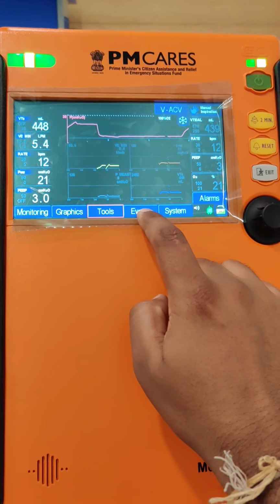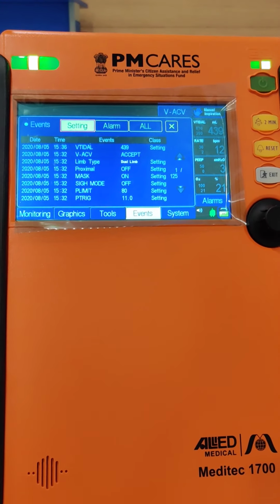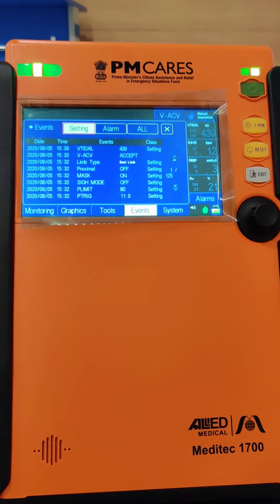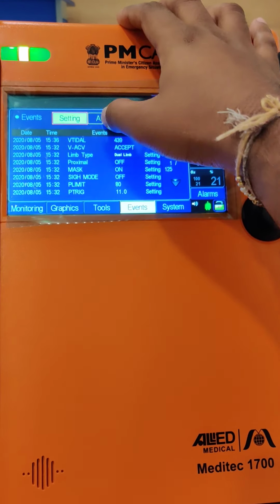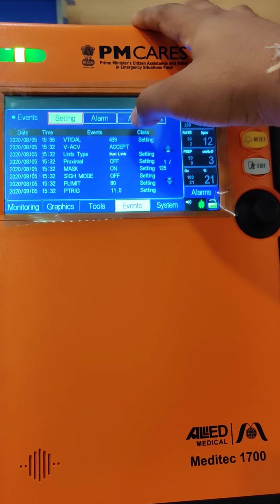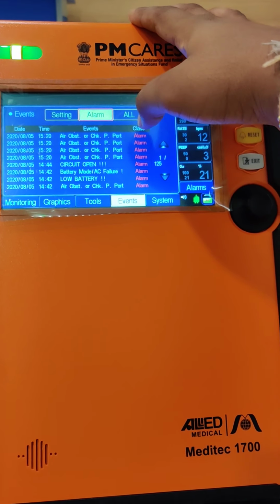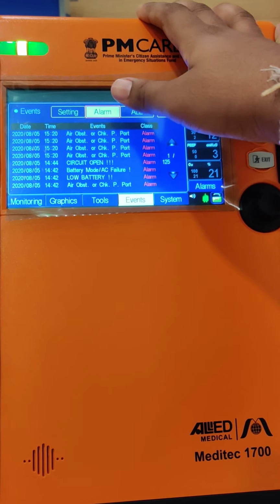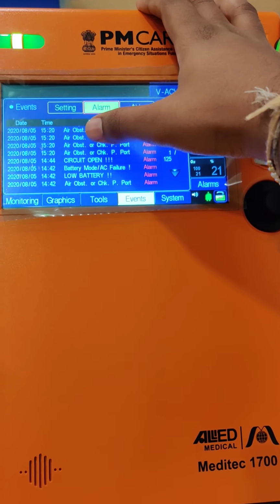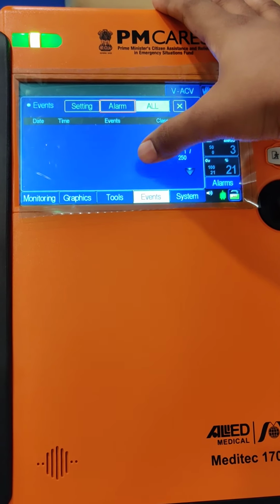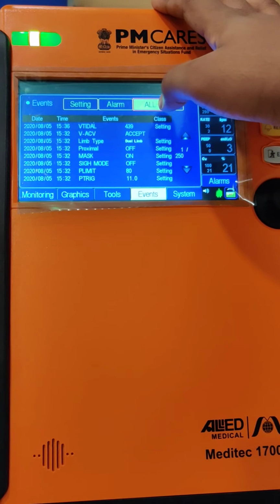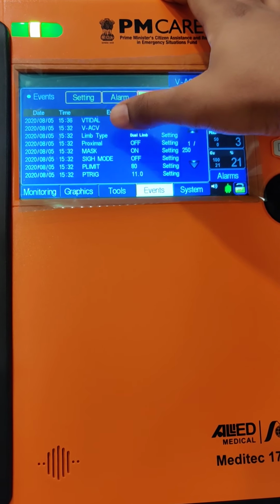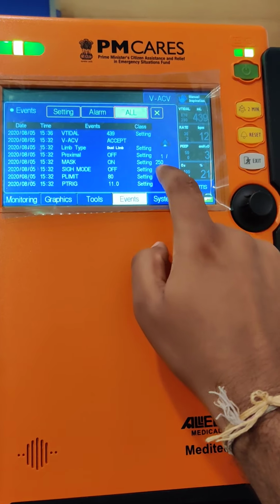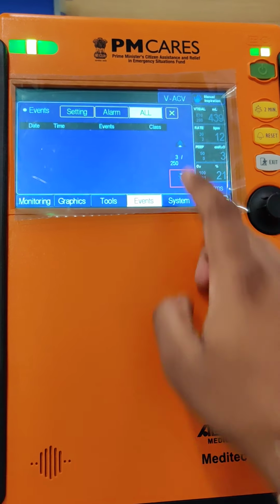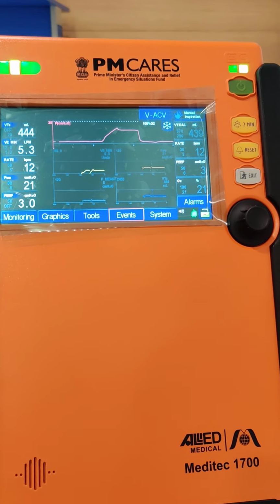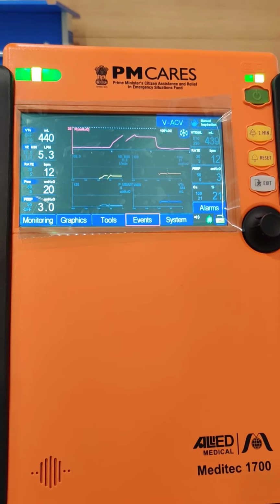Now coming on to the next shortcut key, this is the events. You can see the history logs, both for settings and alarms, whatever settings you have made in the past or whatever alarms have come up. You can see these alarms with the time and the date. If you select the all button over here, you will get the display of both the alarms as well as the settings. It has a 2000 alarm history, so you can see the past history and the alarms which have come up in the events.